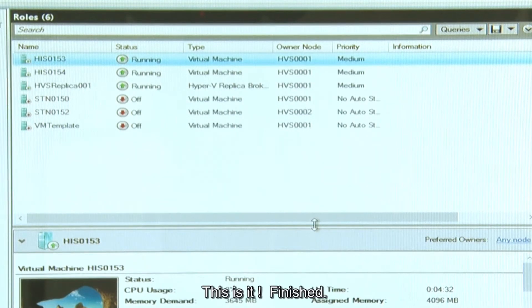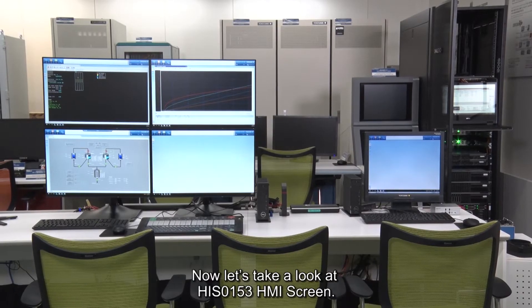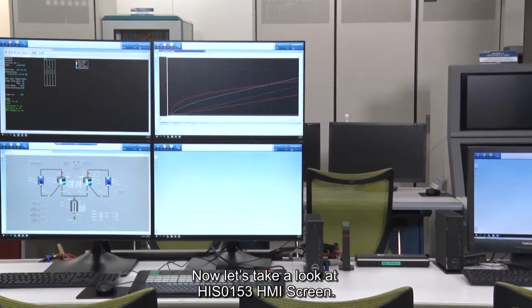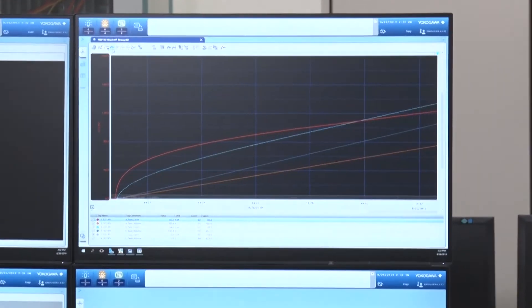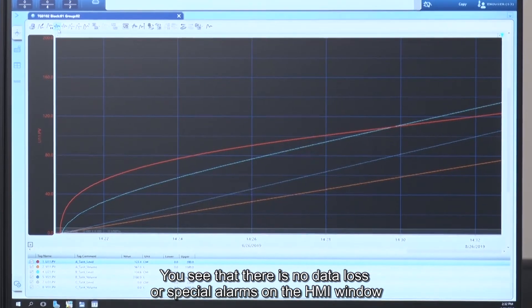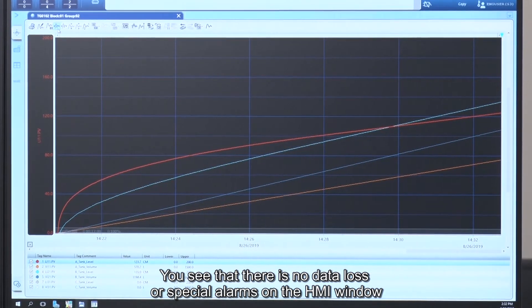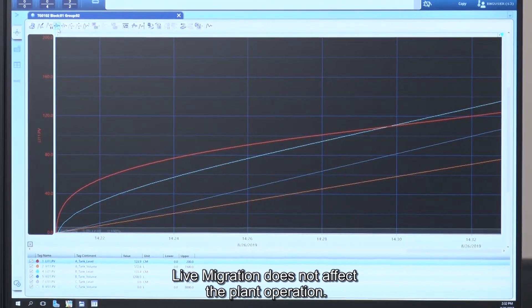That's it, finished, very simple. Now let's take a look at HIS-0153 HMI screen. You see that there is no data loss or special alarms on the HMI window. Live migration does not affect the plant operation.